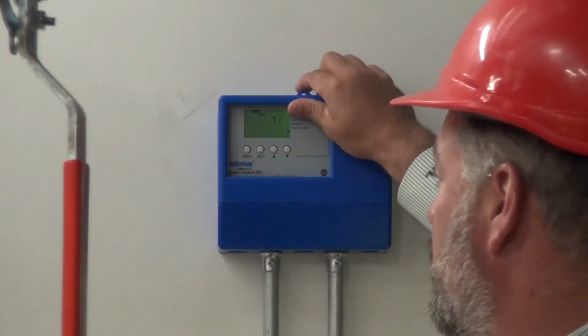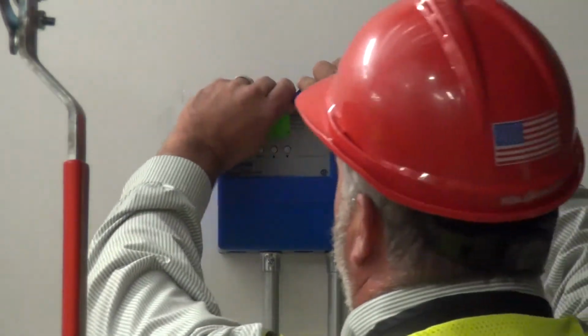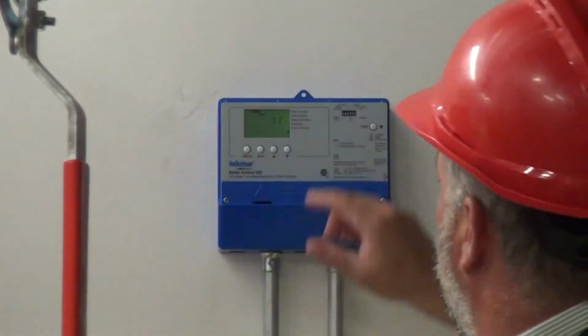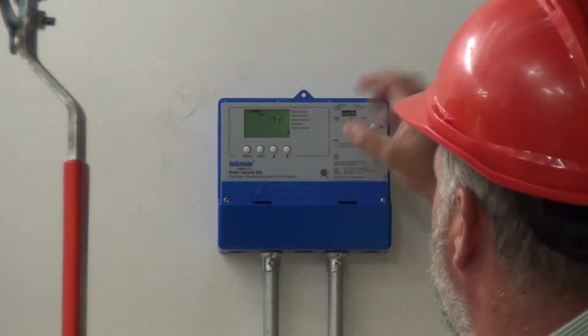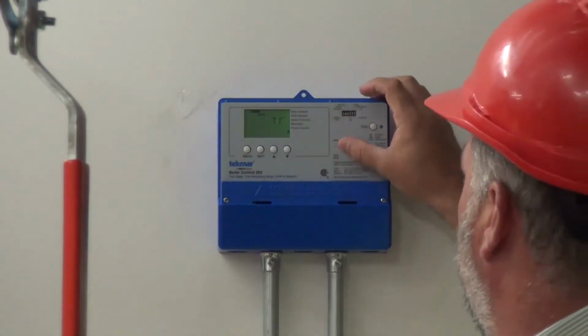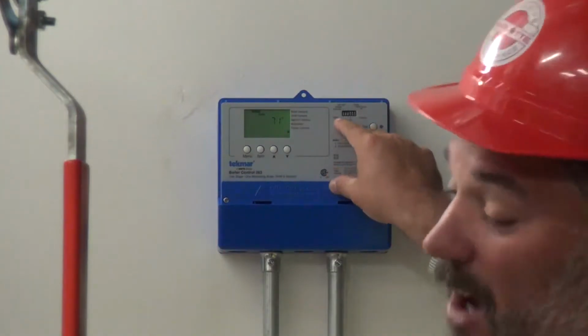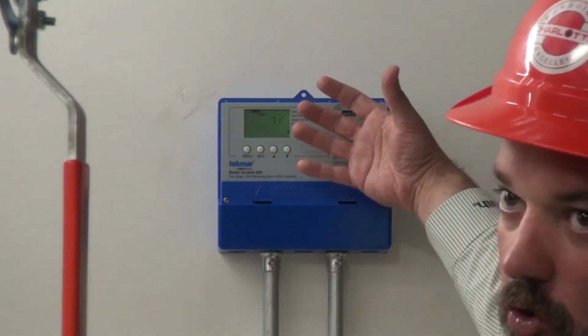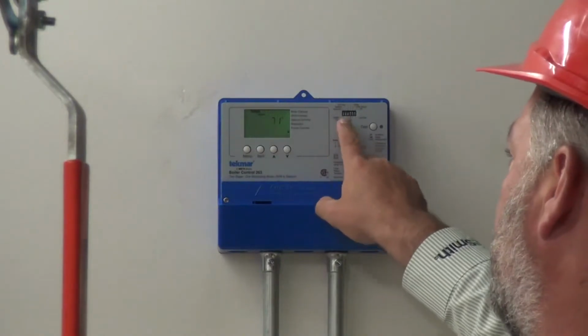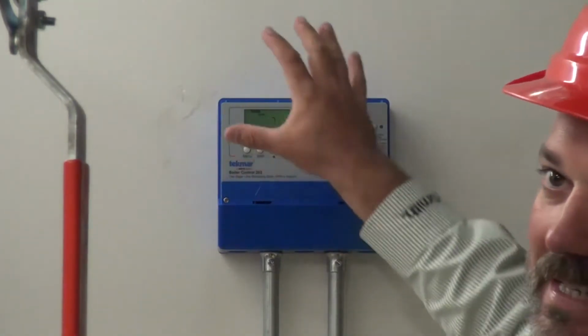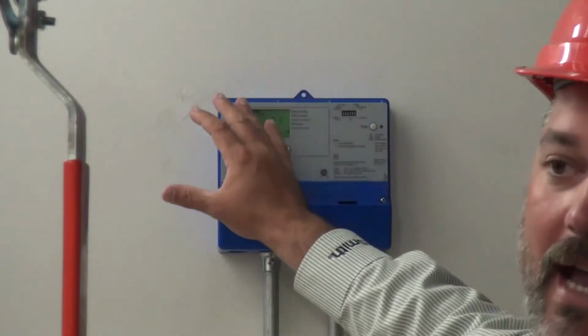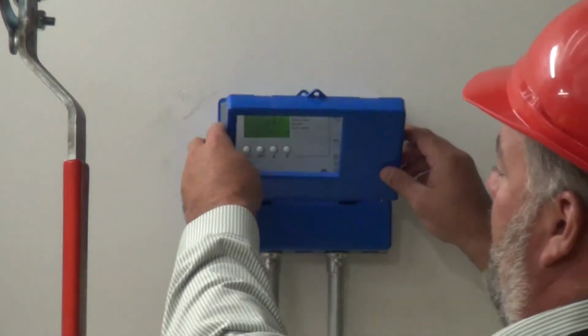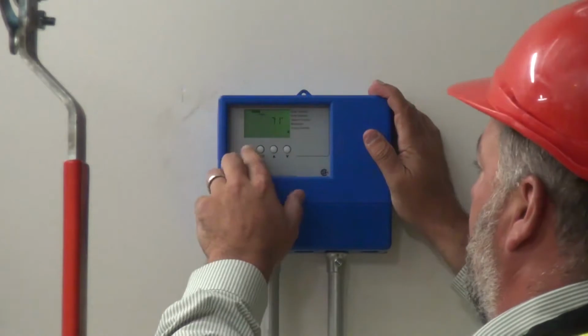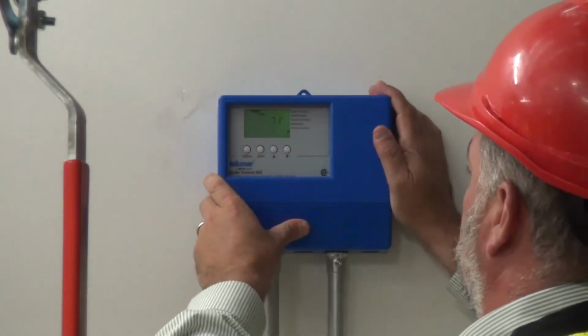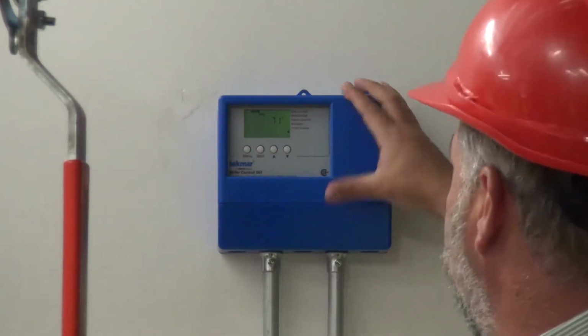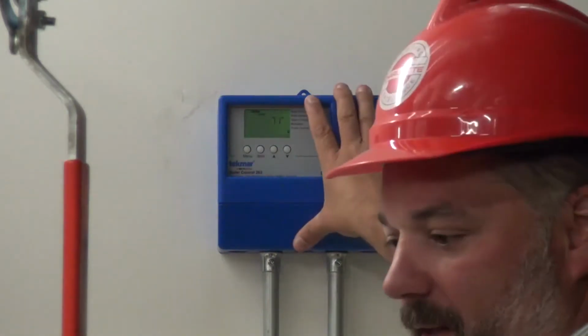There's other things you can do as well. In order to access, you just pop this cover off, and you've got your little dip switches here that basically have been programmed for these boilers. So if you wanted to go to the installer mode, that gets you deeper into the controls, that's where you'd flip that onto installer mode. We turn that on so we could get even deeper into the controls. But for what we're looking at here, it's basically the stuff I went through on there. And that's really what this control is. It's already been set, like I said.